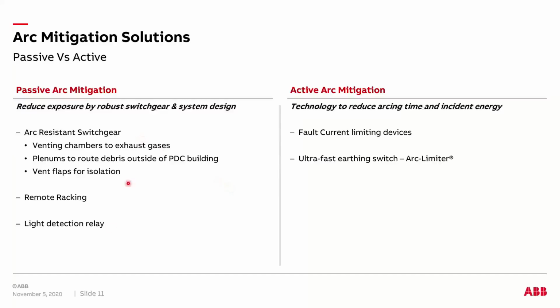And the other solution is a light detection relay. For all these solutions, you have an arcing fault that occurs within your equipment and lingers for at least 80 to 100 milliseconds. So it's a really critical parameter to keep in mind when we are designing our equipment, whether to choose a passive arc mitigation or an active arc mitigation.